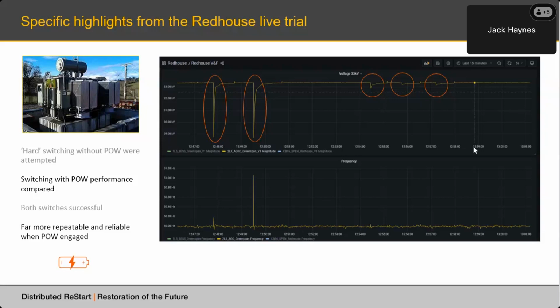It then measures the point on the wave of the live side, and then, understanding the closure time of the circuit breaker, it closes the circuit breaker such that the point on wave of the live side matches the point on wave of the dead side, such that the inrush current is mitigated as much as possible, and you don't see a voltage deviation, or as much of a voltage deviation, as when you're attempting a hard switch or a switch without any mitigating technology. So the two switches you're seeing on the left, highlighted by the orange circles again, that's when we attempted without point on wave. You can see the voltage at 33 kV being pulled down to about 29 kV as a consequence of the inrush current of the transformer.